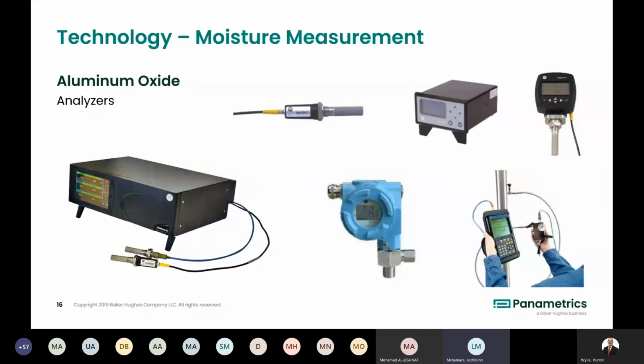So depending on what you need to use it for, the sensor itself will most likely be mounted in a sample system. It's not really recommended to mount it directly into your process pipe, just due to temperature and pressure considerations. These sample systems are something we design and supply as well. So if you want to move on to the next slide, Hunter.